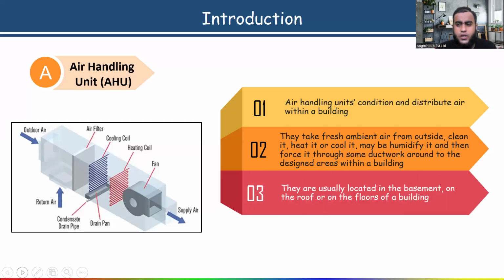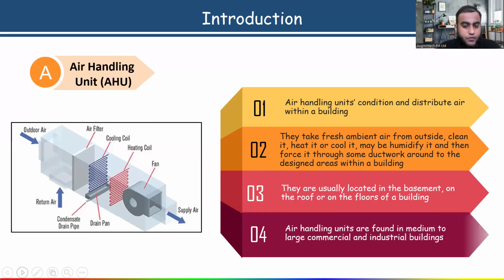So AHUs are usually located in the basement, on the roof, or on the floor of a building. It depends on the situation. If you have a mechanical room, suppose the architect has sent you the drawing, then it is better to install it in the mechanical room. Depending on which type of AHU you are using, sometimes we use floor mounted, ceiling suspended. Air handling units are found in medium to large commercial and industrial buildings. So is it clear? All of you tell me. The purpose of the AHU is clear from here.